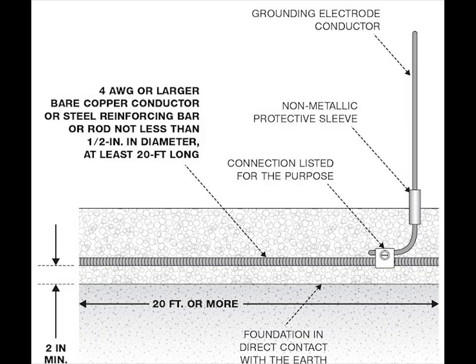The house requires the electrical system to be grounded. This means actually in the ground. I elected to use a system known as an Ufer ground, which is an electrical earth grounding method. It is often used for structures with concrete foundations. It was developed by Herbert G. Ufer in 1942, and in 1968 was first permitted in the National Electrical Code. In 1978, the code was modified to allow for half-inch rebar to be used as the grounding electrode.